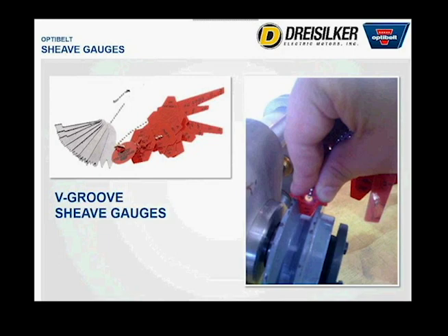They have something called a V-groove sheave gauge. It has a plastic profile of what the groove is supposed to be like under ideal conditions. You put this in the groove in multiple places, like shown in the picture, shine a light behind it, and see if light leaks out. If the sides of the pulley are uneven, shiny from polishing, or show uneven wear, it's about time to replace your pulleys, because when the belt contacts that uneven wear, it will get damaged over time and fail early.